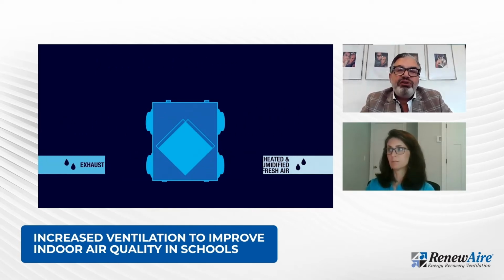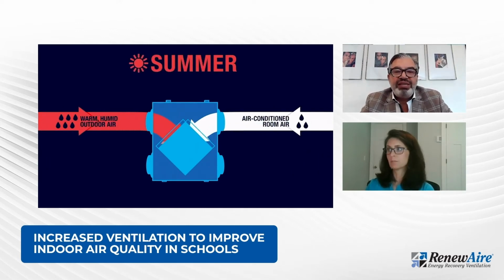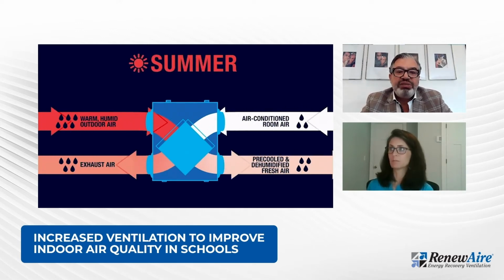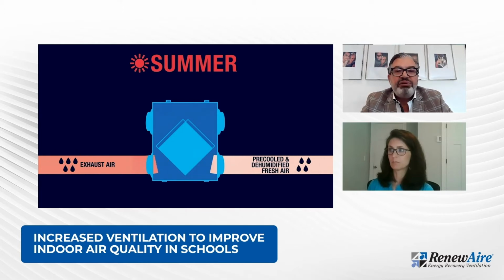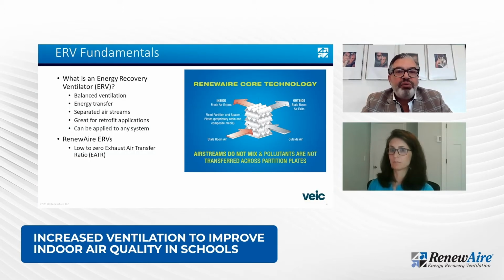Now, because we're using an enthalpic core, there's an actual physical separation of the airstreams, meaning that the airstreams do not touch each other. So that assures next to zero cross-contamination, or less than 0.1% cross-contamination. And depending on how the consulting engineer and the contractor set the pressures and parameters, we're able to assure zero cross-contamination. So these systems would be great not only for new buildings, but also for retrofit applications.